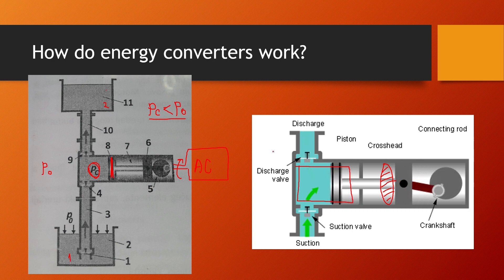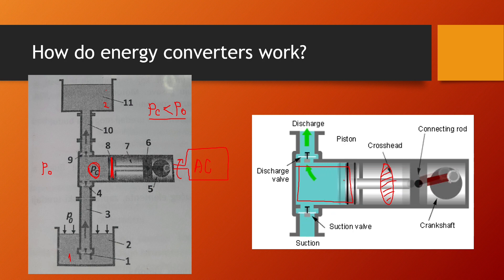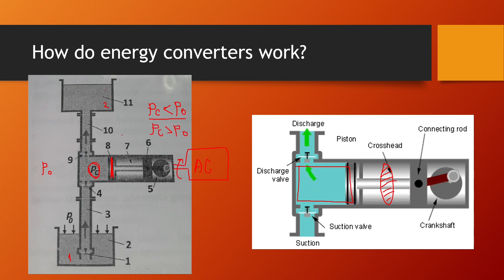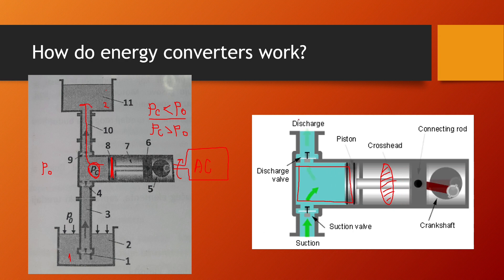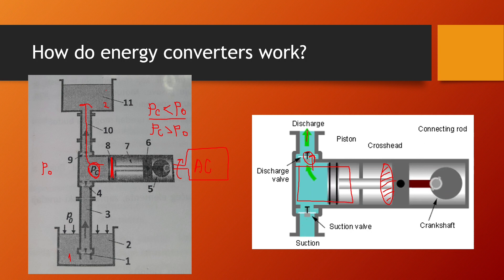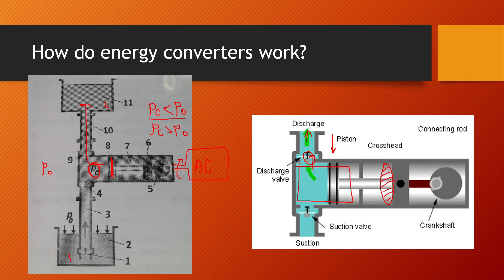When the work volume fills with liquid, the piston starts moving left. As the volume lowers, the pressure rises. When the piston reaches the maximum left position, the pressure is greater than atmospheric pressure. This higher pressure drives the liquid up through to reservoir two. The two valves control the flow — the discharge valve opens when fluid pressure pushes it up, allowing fluid to move upward, and the valves prevent fluid from coming back due to gravity.